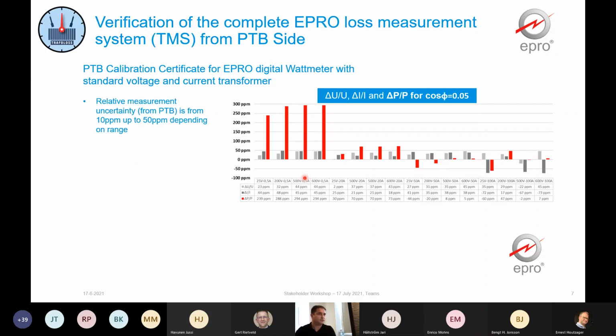And last but not least, I want to show some facts about the complete EPRO loss measurement system. On the graph, you can see one part of the calibration certificate from PTB from 2014. One part, because here I show only the results from the lowest power factor we could calibrate at PTB, and that's the 0.05. At higher power factor, the results are naturally better. Anyway, this calibration is related to our digital wattmeter with standard voltage and current transformer. The ranges here were for the voltage channel from 5% to 120%, and for current 1% to 200%.